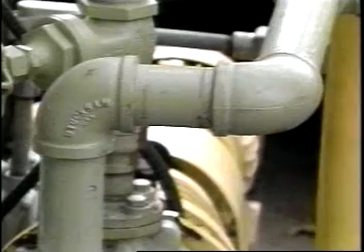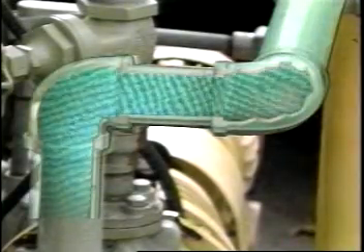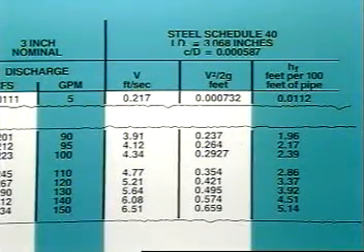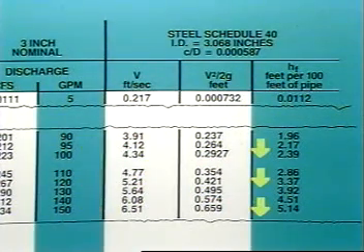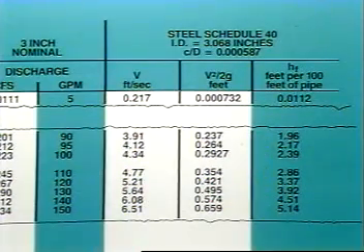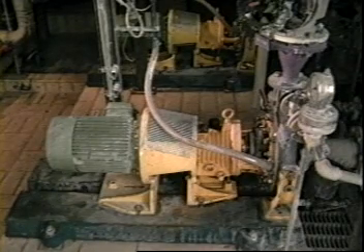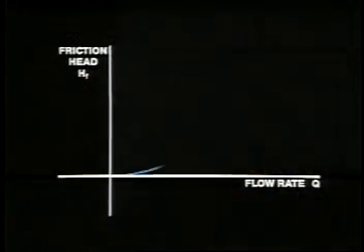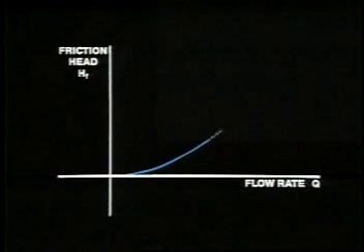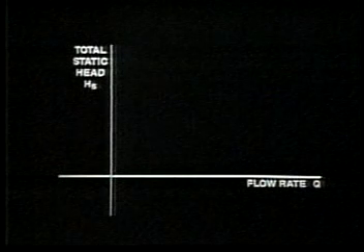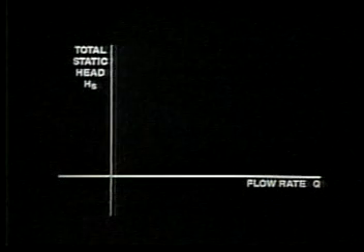Friction loss is the resistance to flow in the piping system. Its total amount can often be obtained from a set of friction loss tables. As the flow rate through the pipe increases, the friction loss also increases, but at a far higher rate. Friction head is the energy required to overcome friction loss. Comparing the friction head against the flow rate, the curve will appear as shown — as the flow increases, the friction head also increases.